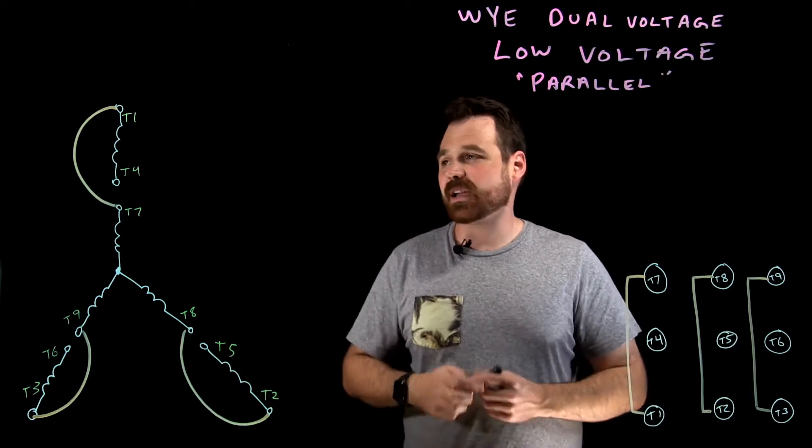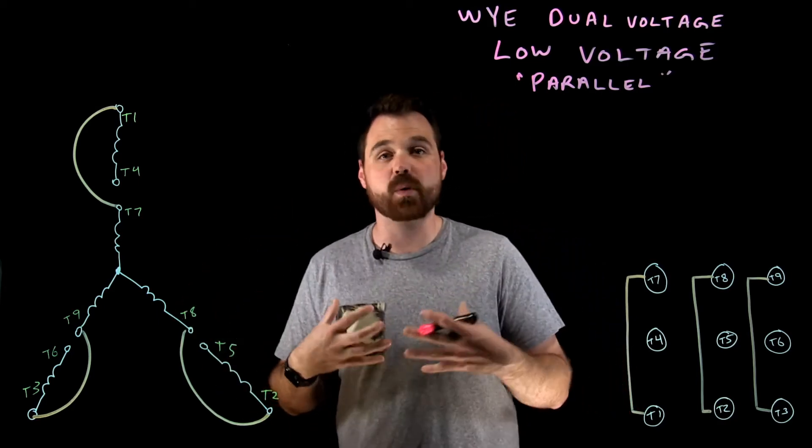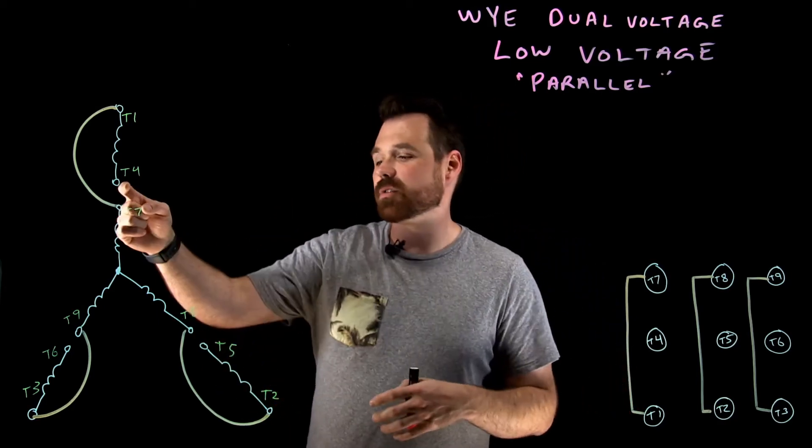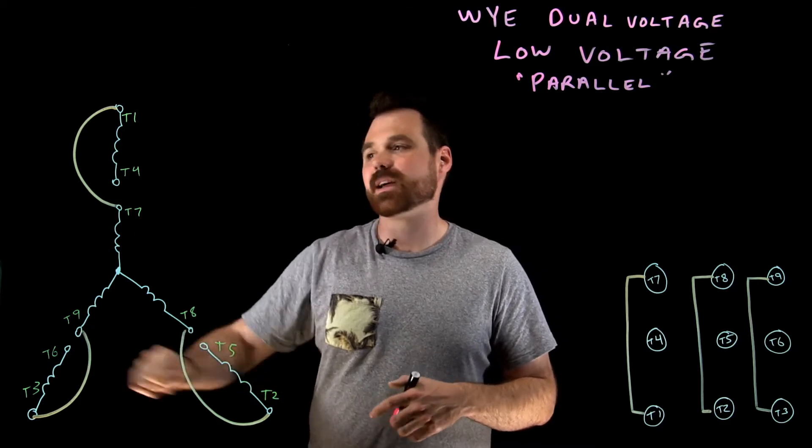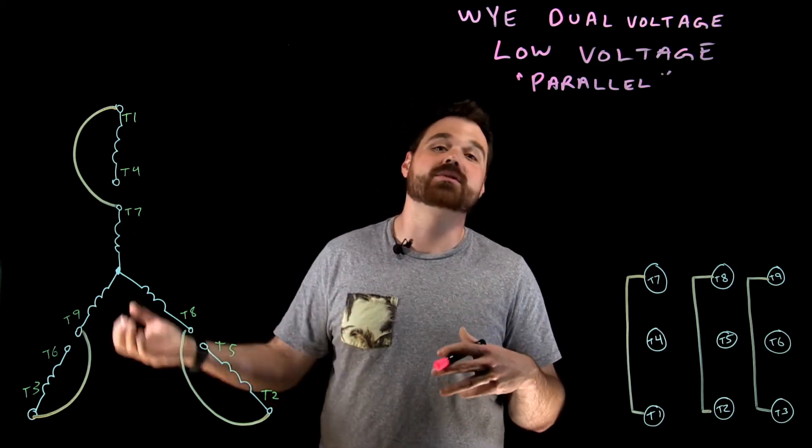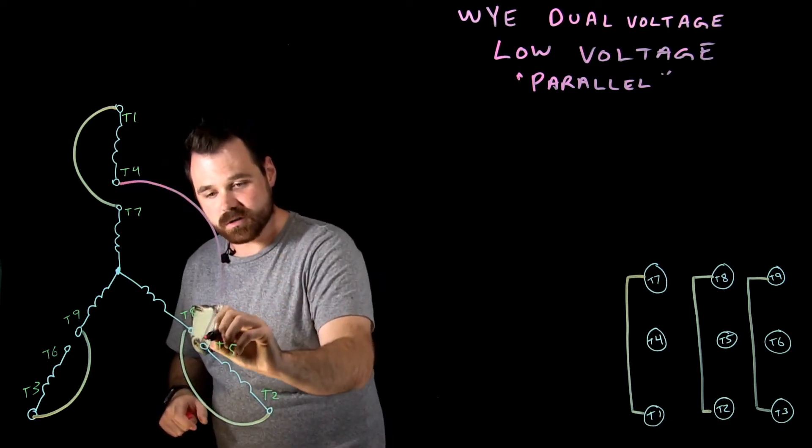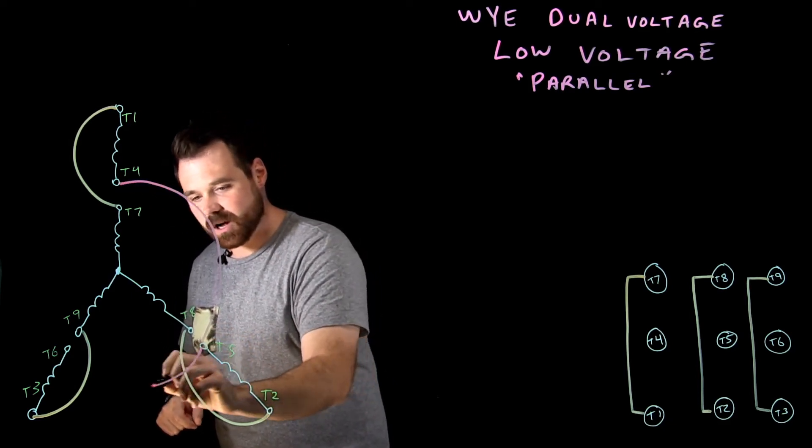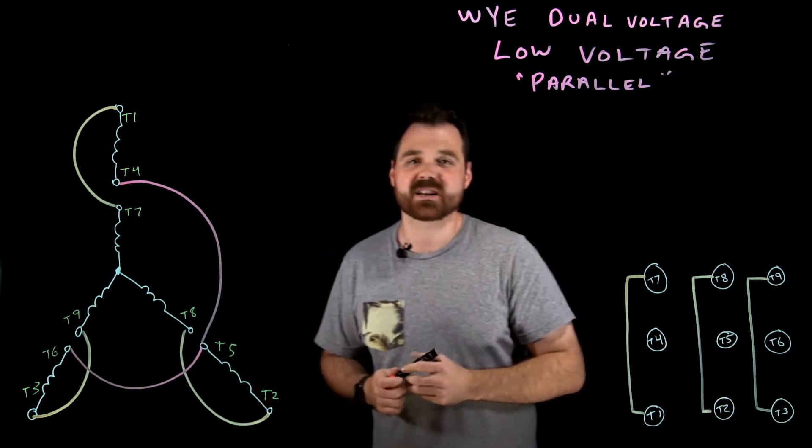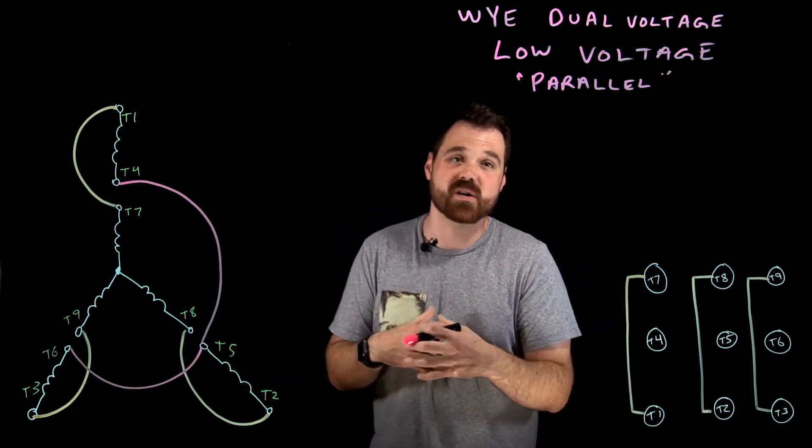Now step two is I need to make a Y point, or a star point, with T4, T5, and T6. I'm going to bring those together and connect them up. I'm going to go T4 to T5, and then T5 to T6, connecting those up into a star point.